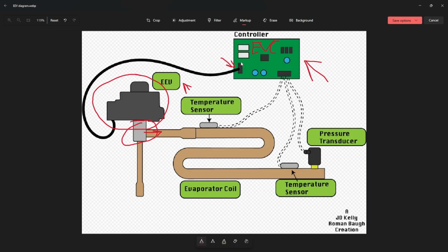On top of the main wire that connects to our stepper motor, we have a temperature sensor here and a temperature sensor here. For Trane, those sensors are going to be called your gas temperature sensor, which is this one. You'll see it referred to as GT. And then your evaporator temperature sensor. You'll see it referred to as ET. So you have evap temp, which monitors the temperature of our coil, and then you have a gas temp sensor, which monitors the temperature of the refrigerant leaving the evaporator coil, which is why it's called gas temp. Because remember, going out of the evaporator coil, we should have a superheated gas refrigerant heading to our compressor. This would be our suction line right here.